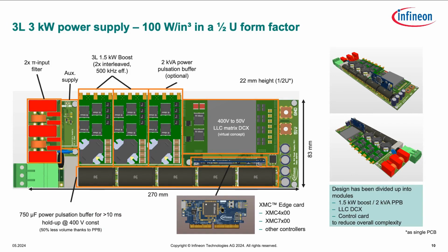Let's start with the power factor correction stage. We recently demonstrated a 3-level PFC stage, achieving 3 kilowatt in half a U height. The height of this demonstrator is only 22 millimeter. We can stack 2 of these boards in order to reach 6 kilowatt power, which clearly supports the trend in server power supplies to move from around 3 kilowatt into 5, 6, or 7 kilowatt in the near future. As the topology is a 3-level PFC stage, we can use lower voltage rated devices. In this case, we're using our brand new 400 volt rated silicon carbide MOSFET.